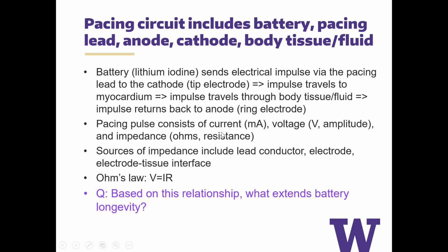The pacing pulse consists of current, which is measured in milliamps. Voltage is also called amplitude, and that's measured in volts, obviously. Impedance is a measure of resistance, and the unit for that is ohms. Sources of impedance include the lead conductor and the electrode to tissue interfaces. Basically, anywhere the electricity has to pass through will be a source of impedance or resistance. If you recall Ohm's law, where voltage equals current times resistance, V equals IR, based on this relationship, what do you think will extend battery life?